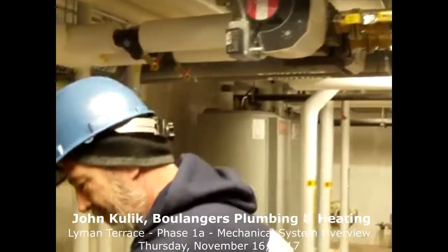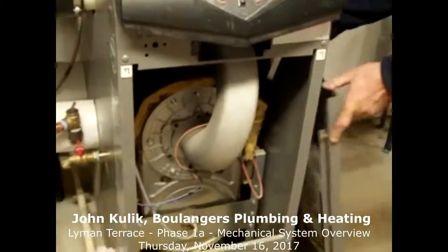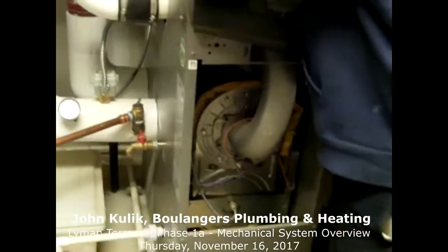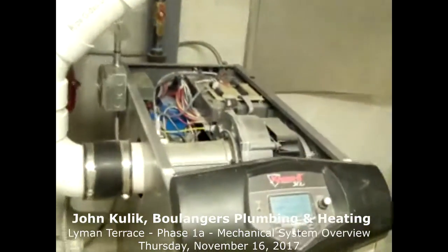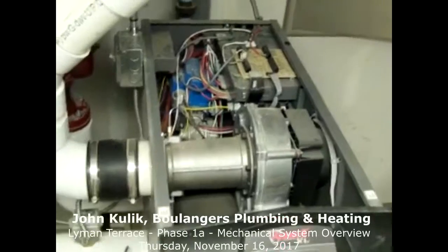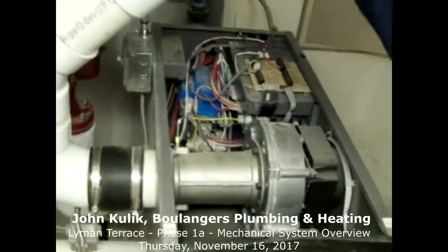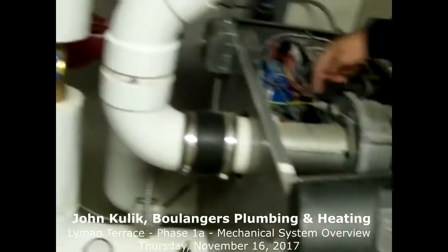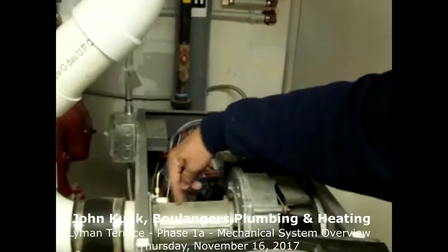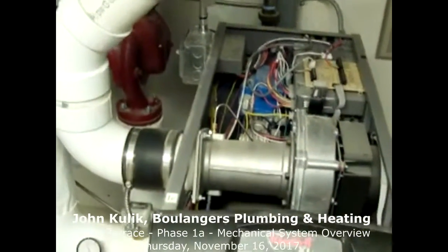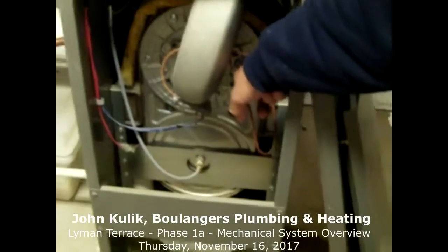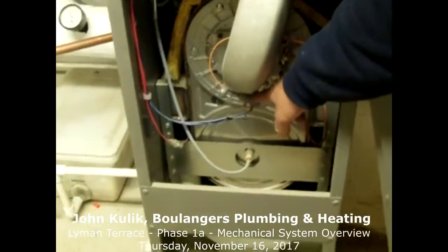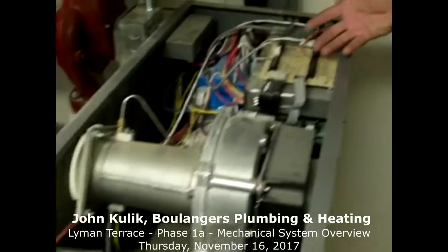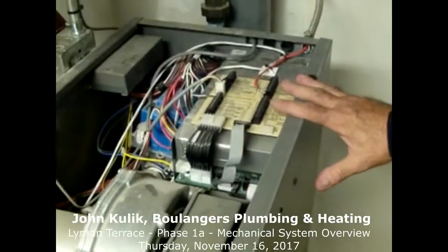Again, we'll take the front cover off. Take the top cover off. You can get a good overview of what the boiler actually looks like inside. This is a draft motor. This draws fresh air in from the outdoors, comes through. Tied in with that is the gas line. This mixes the gas-air mixture to be delivered down a delivery tube in through a burner and ignited by this device here, again, the electrode. Proved to be running by this device, the flame sensor. All goes back and ties in to the main control circuitry here. This is the brain of the operation. Okay, everything leads back into this, proving that it's all working.